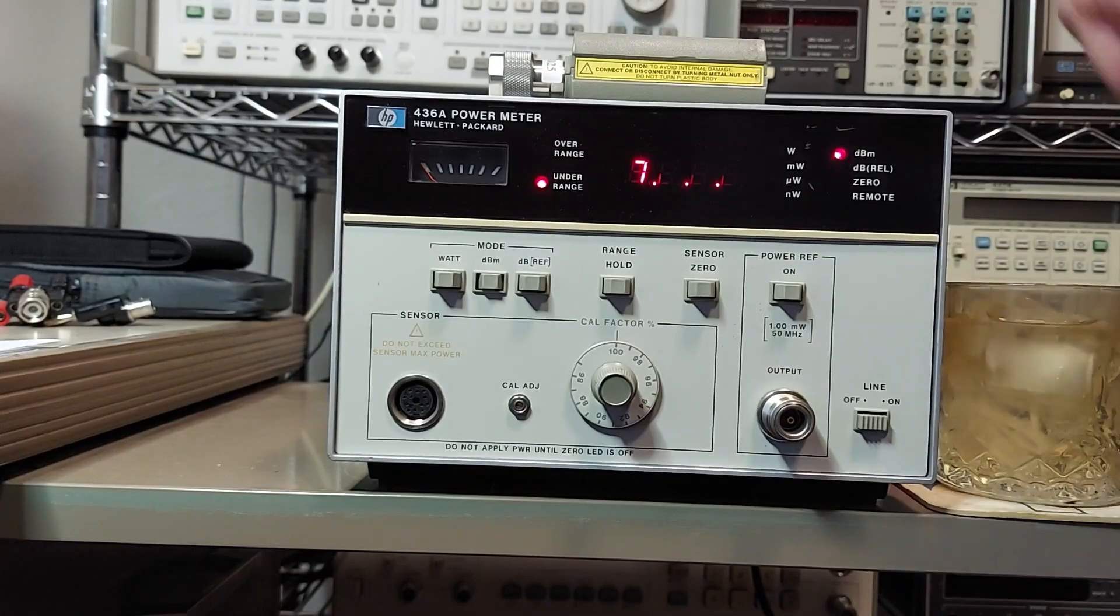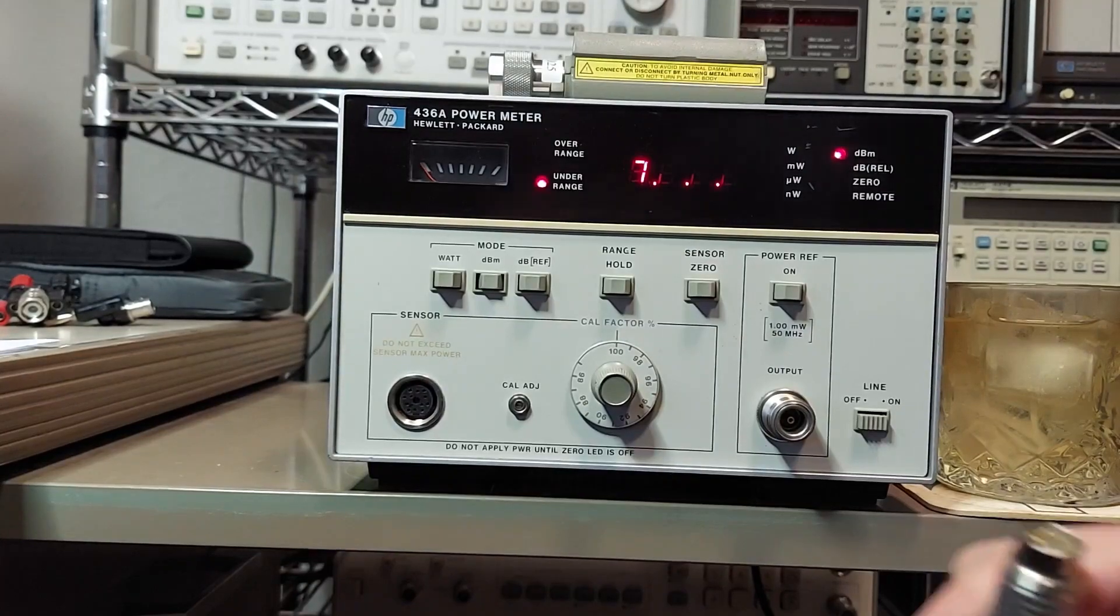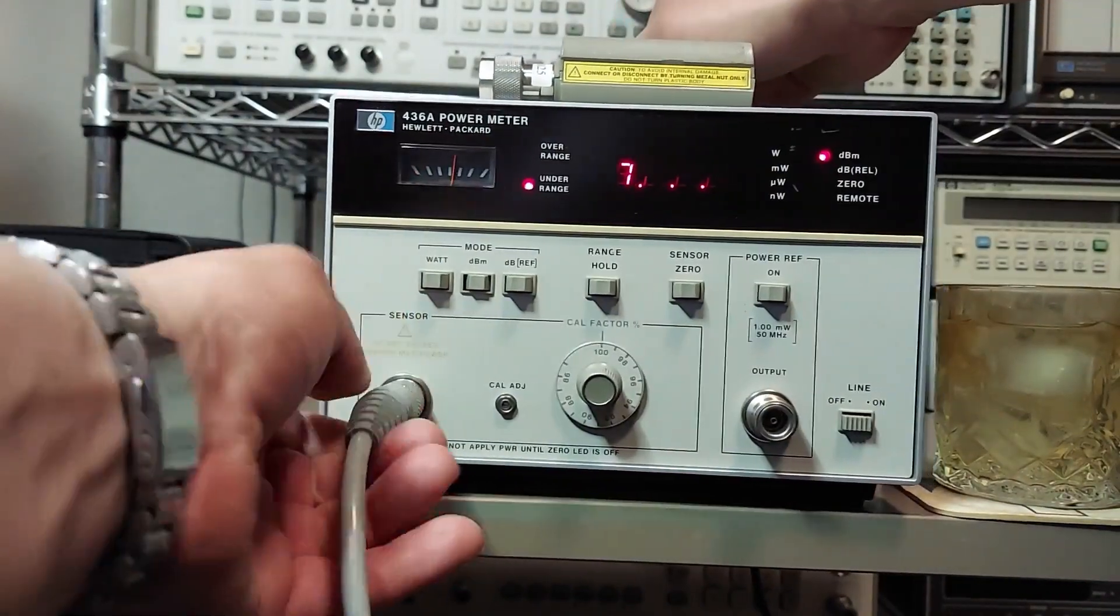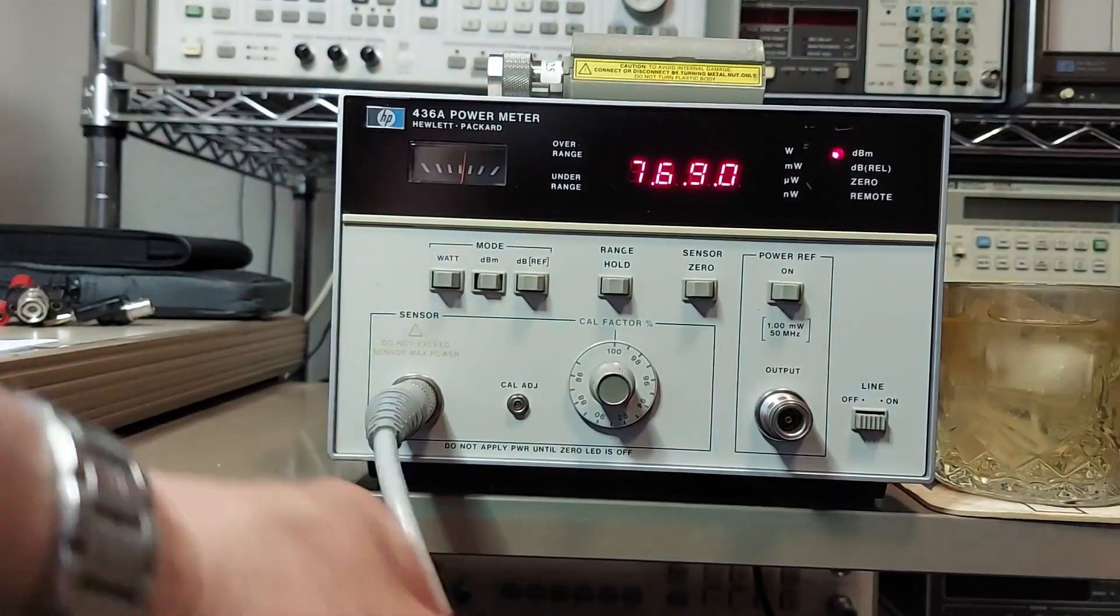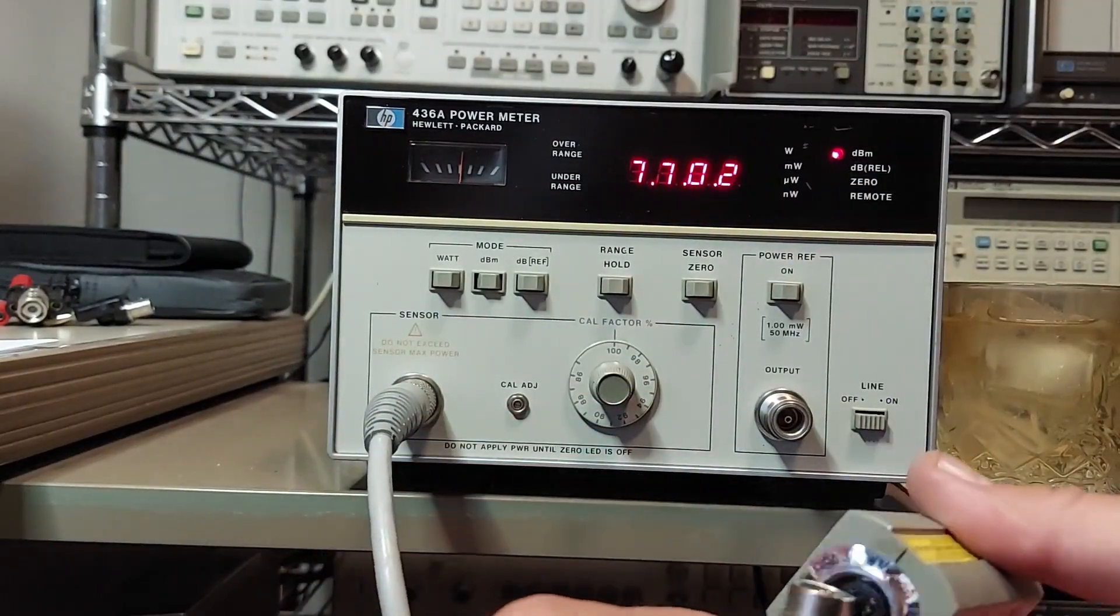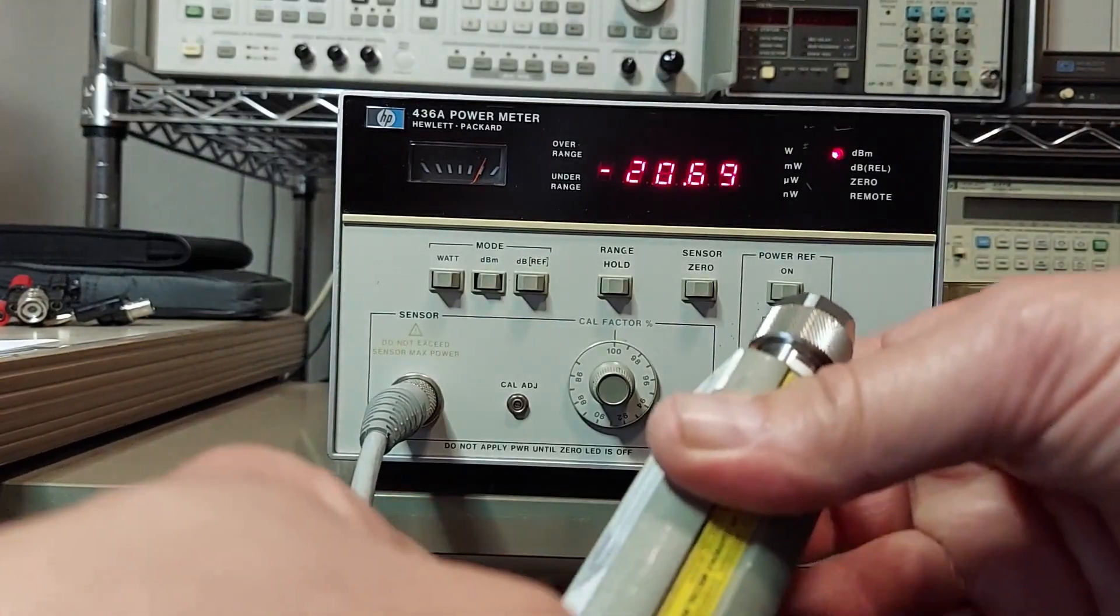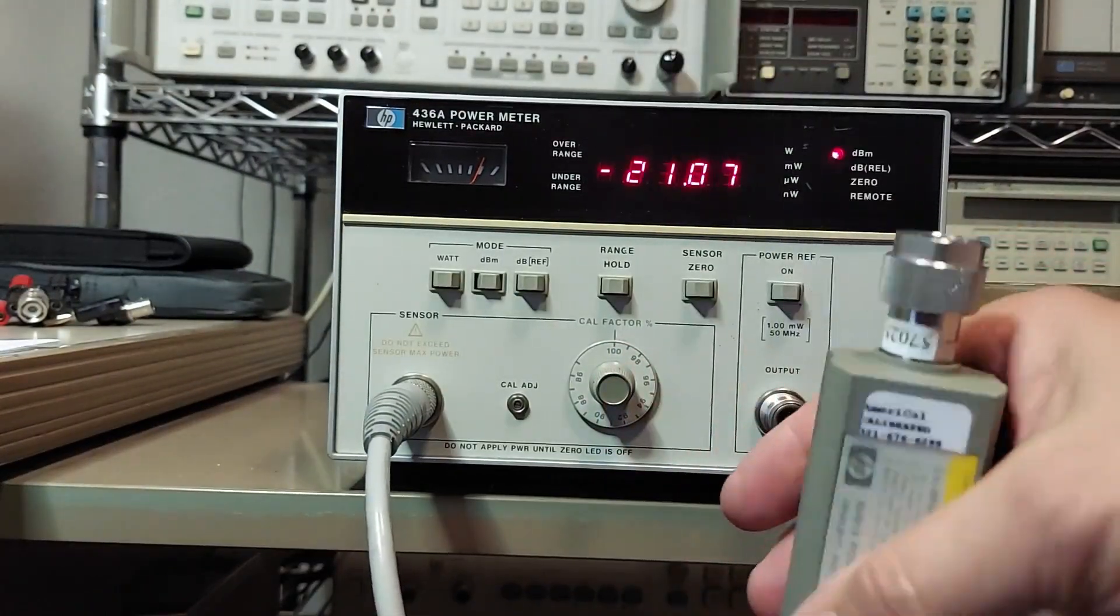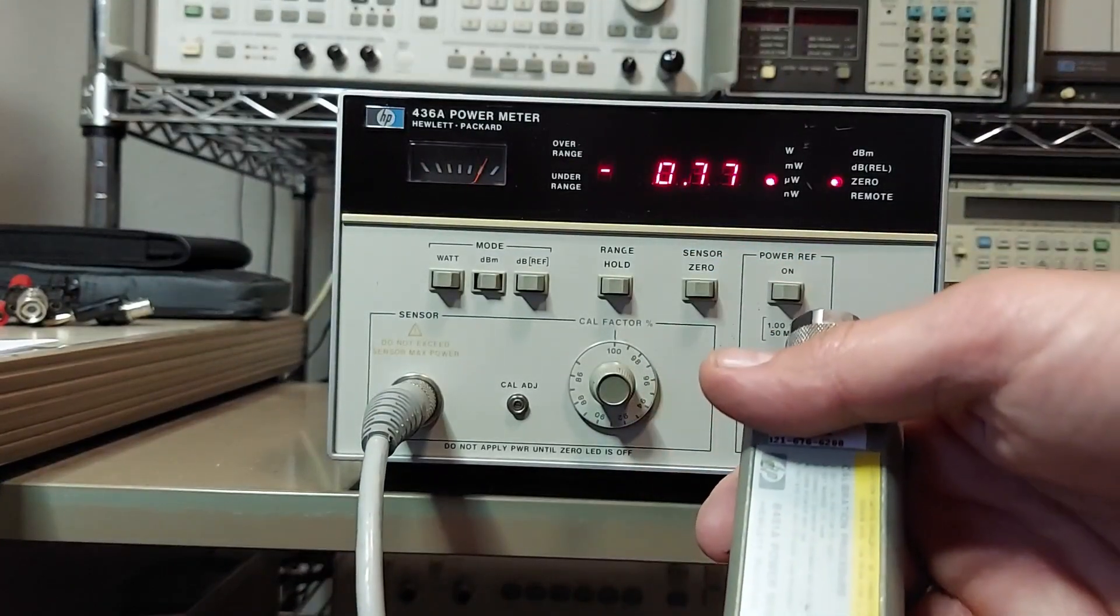So on this power meter, to get your power sensor ready, we'll hook the cable up to the unit here and plug our power sensor in. Now the first thing you're going to need to do is you're going to have to zero the power sensor. So we press the zero button.